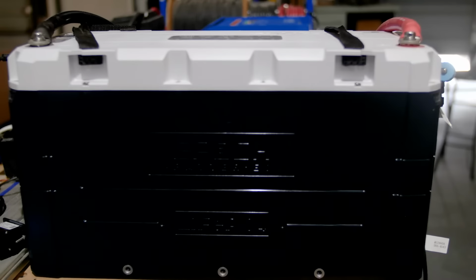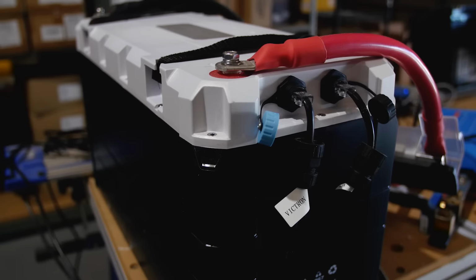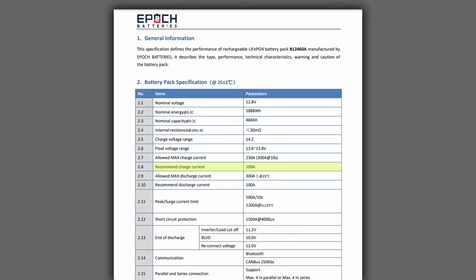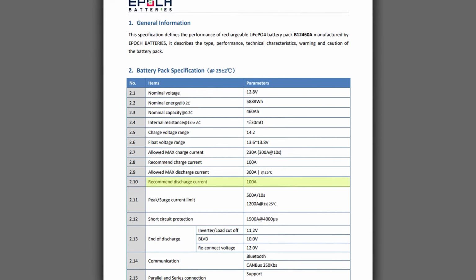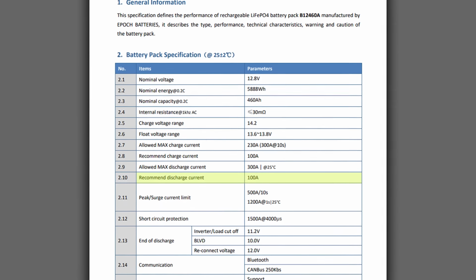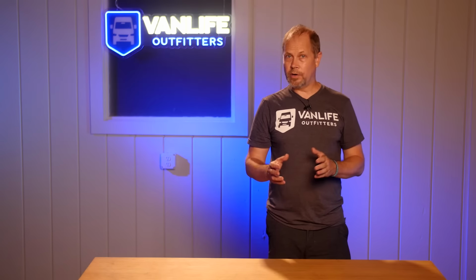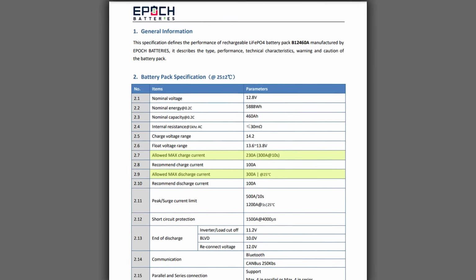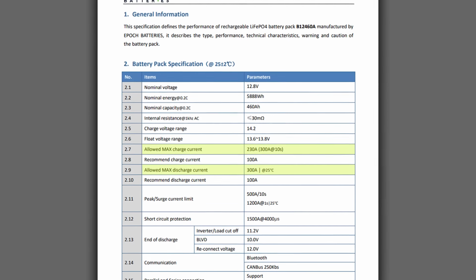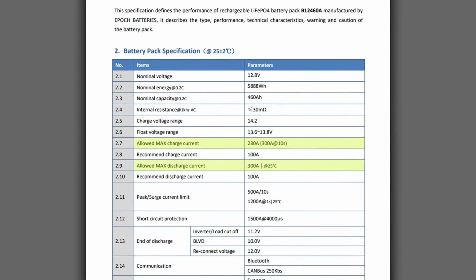And just like the storage capacity, when you put more than one battery into a bank, wired in parallel, these throughput capabilities are added together. As an example, this Epoch 460 amp hour battery has a recommended continuous charge current of 100 amps and a recommended continuous discharge current of 100 amps. Or, for short periods of time, a maximum charge rate of 230 amps and 300 amps for discharging.